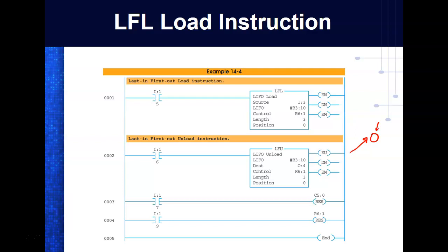So what we would have to do is use this to establish where we want the top of the stack to be. Does that make sense? And remember, we use the B register a lot. We use the B register for internal relays. We use a B data file for internal relays. And a stack can definitely wipe out stuff, right? Because once you push stuff on the stack, if you don't keep up with where the stack's at, it'll just wipe out whatever data file contents you have there.